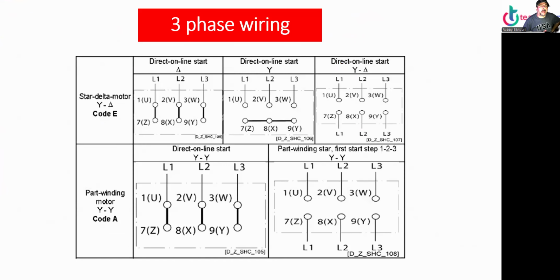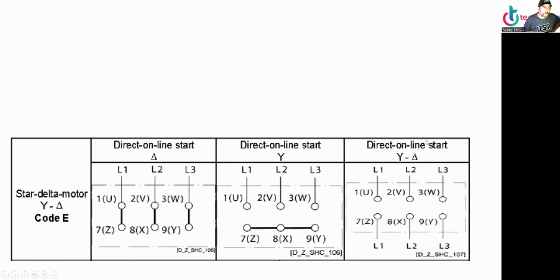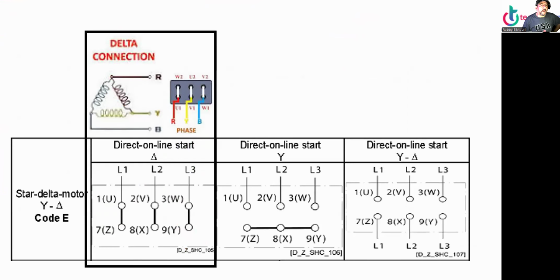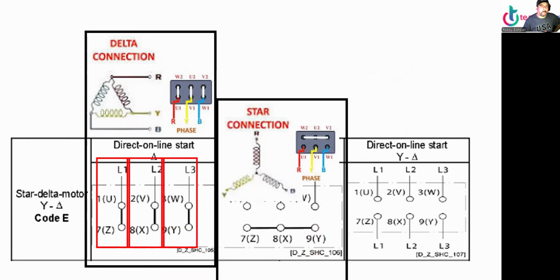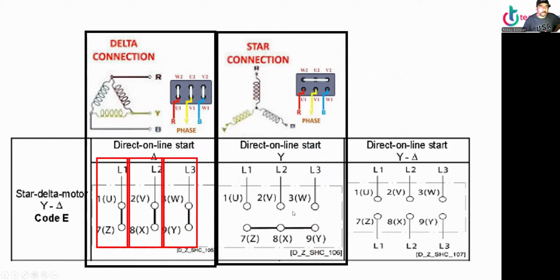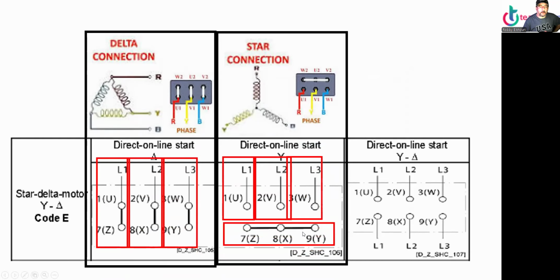Alrighty, let's move on to electrical now. 3-phase wiring. All right, so we have a delta connection. According to this diagram, you can see L1 connects to 1 and 7, L2 to 2 and 8, and L3 to 3 and 9. Now, in this connection, we have L1 to 1, L2 to 2, L3 to 3, and 7, 8, 9 together. They go nowhere, just together.